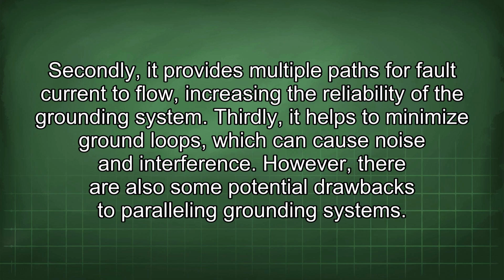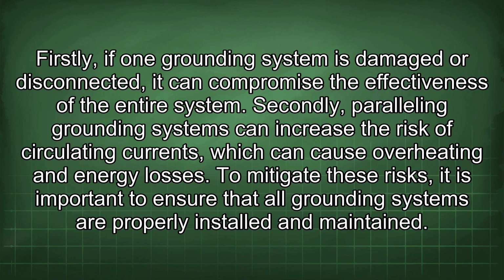However, there are also some potential drawbacks to paralleling grounding systems. Firstly, if one grounding system is damaged or disconnected, it can compromise the effectiveness of the entire system. Secondly, paralleling grounding systems can increase the risk of circulating currents, which can cause overheating and energy losses. To mitigate these risks, it is important to ensure that all grounding systems are properly installed and maintained.